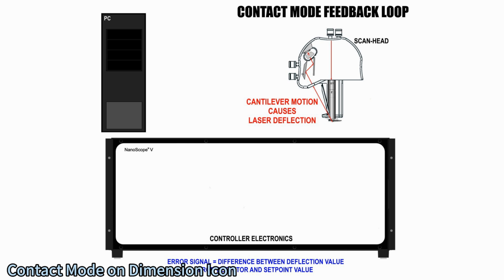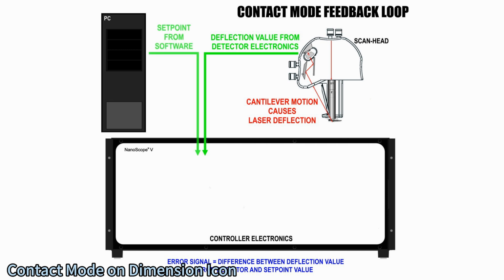The user enters a set point value through the software interface that represents the desired amount of deflection or force on the probe. The signal from the photodetector is compared to the deflection set point, and the resulting difference is known as the error signal.